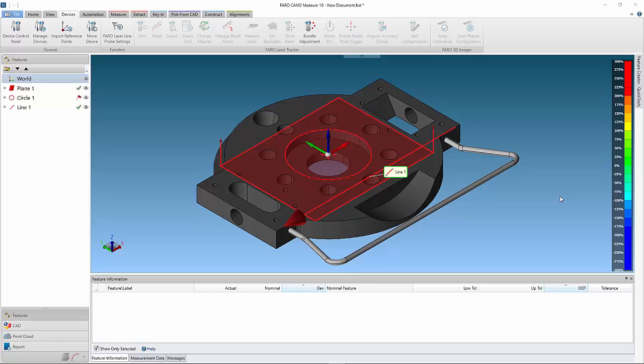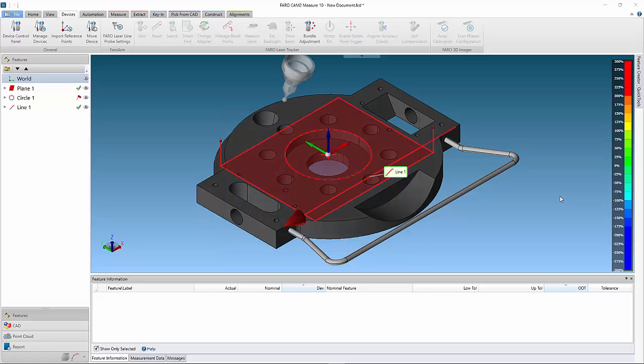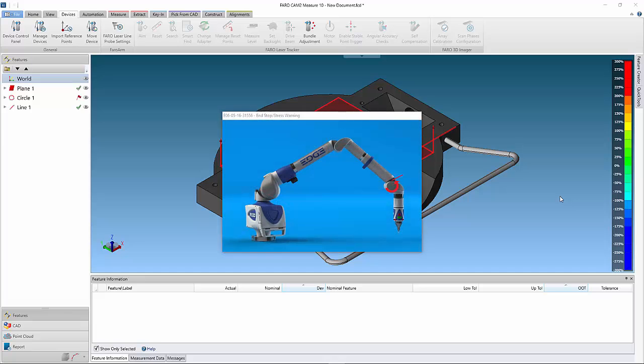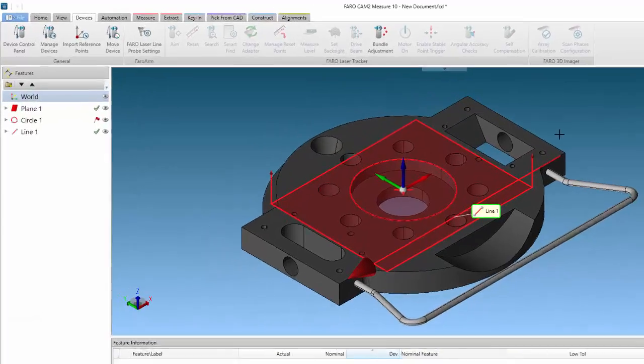First, we have to measure a minimum of 3-point reducible features, towards the limits of our measurement range. The features should create as big a triangle as possible, to ensure the best relocation result. Here we shall measure two circles, and 1 point. If using attachments to create reference points, it is essential that the features used are firmly fixed, or are a physical part of the component.